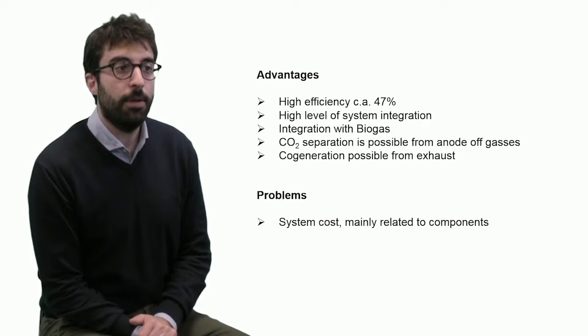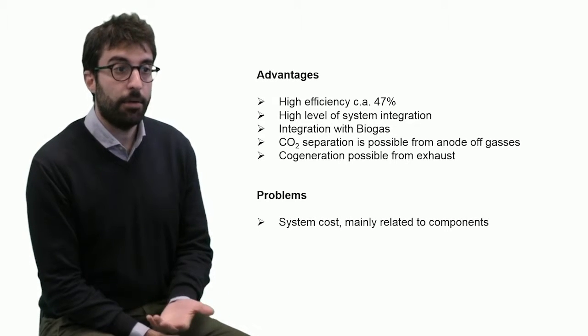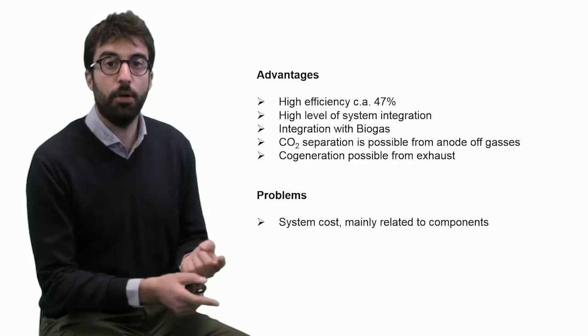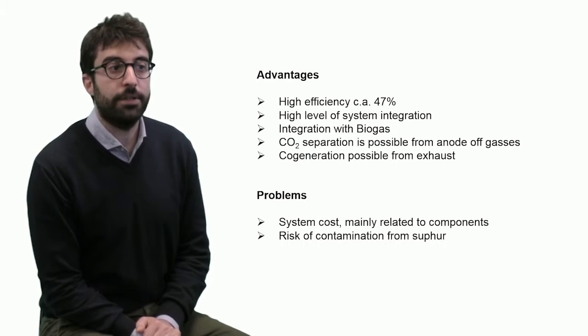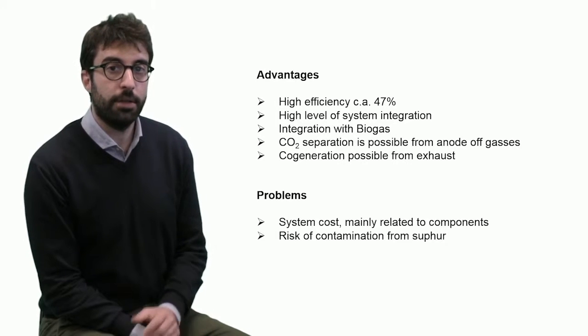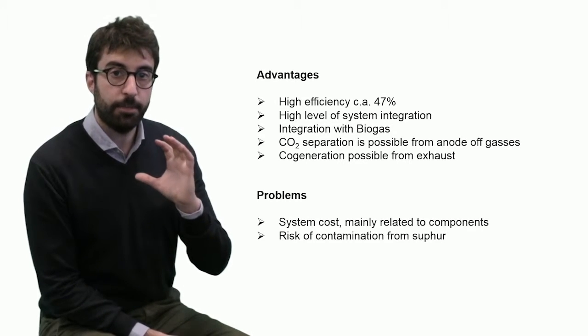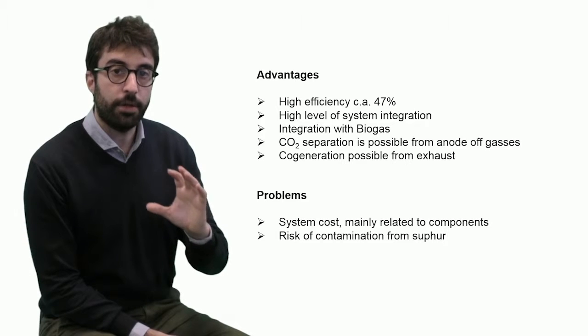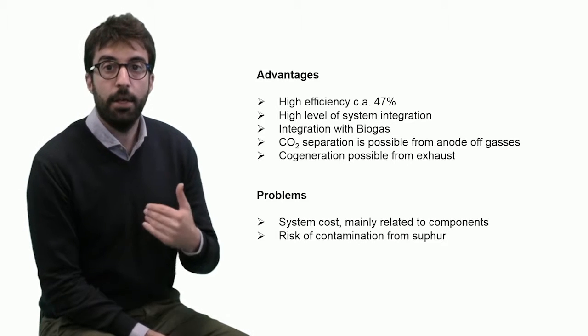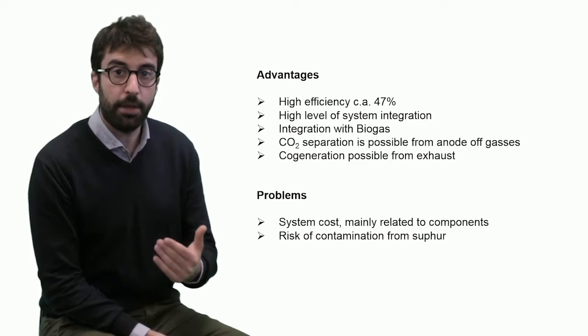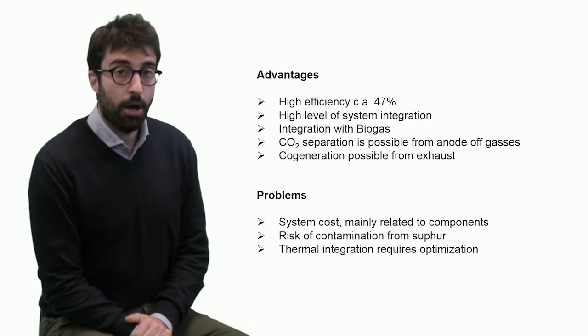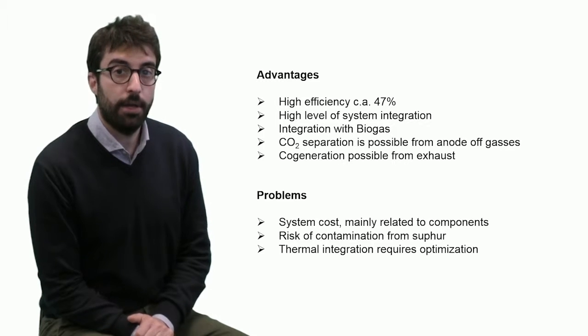There are of course also open issues or problems. Till now, system cost is mainly related not to molten carbonate fuel cells, but to all the other components and the integration of this kind of system, and the risk of contamination from sulfur. We saw that desulfurization is introduced in the system, and this becomes an extremely important component, because any sulfur that gets to the reformer or to the fuel cells generates a very quick degradation of performance with no chance to recover. As I told, the thermal integration requires high optimization.